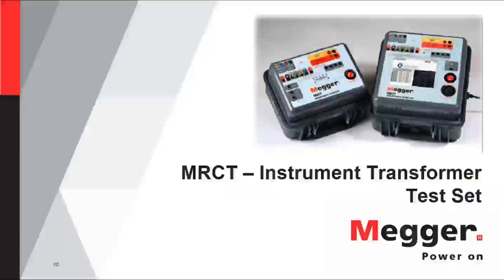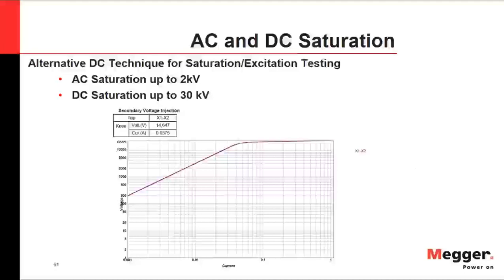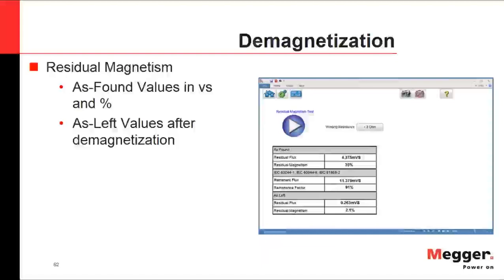Let's talk about the MRCT, Megger's instrument transformer test set. This device supports both AC and DC saturation. The alternative DC technique for saturation/excitation testing allows AC saturation up to 2 kV and DC saturation all the way up to 30 kV. In a field example shown, a CT was tested with a saturation knee point of approximately 20,000 volts.